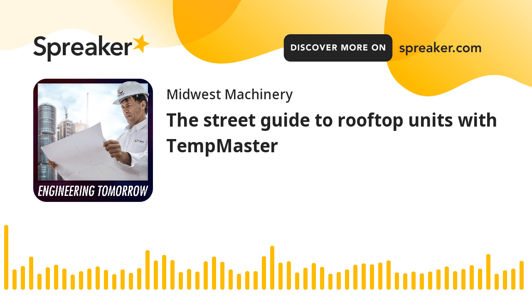So with the refrigeration system, when we're talking about serviceability, one thing that I like to think of with our rooftop units and building them for the future is not only serviceability being reactive, but being proactive. So if you have refrigeration fault detection diagnostics, and that's a mouthful if you don't know what I'm talking about, but basically we have temperature sensors and pressure transducers on the refrigeration system that are plugged into the control system of the unit. Now, if you're a guy that's worked on rooftops, you know that if there's something wrong in the refrigeration system, the first thing they do is take those measurements to figure out what's going on, and they do some calculations, and it helps them understand whether refrigerant is low or overpressurized, or you've got a freezing coil, what have you.